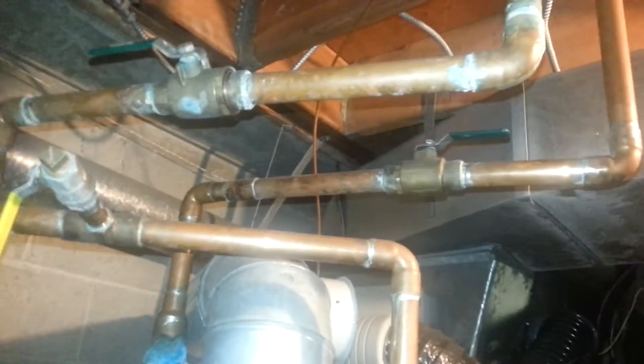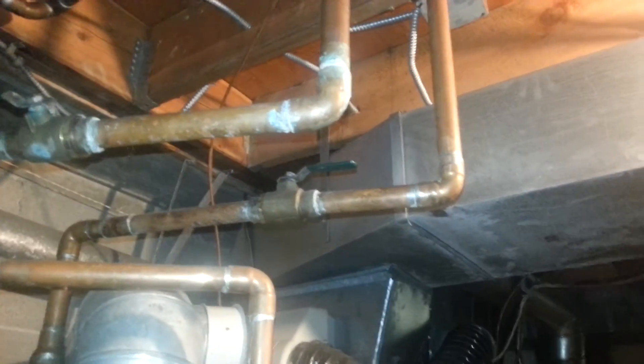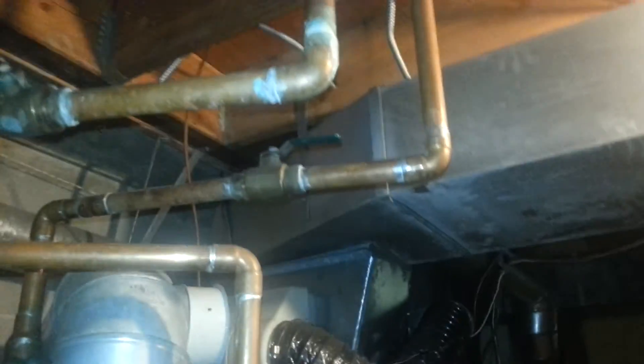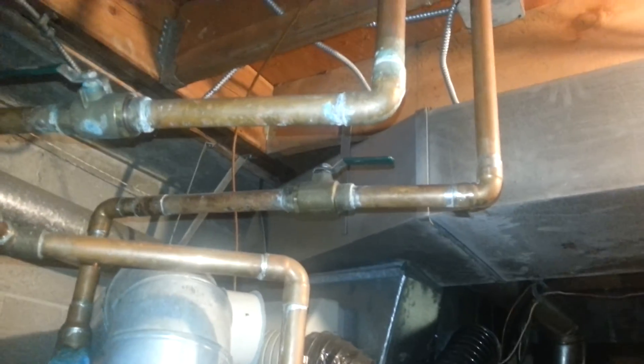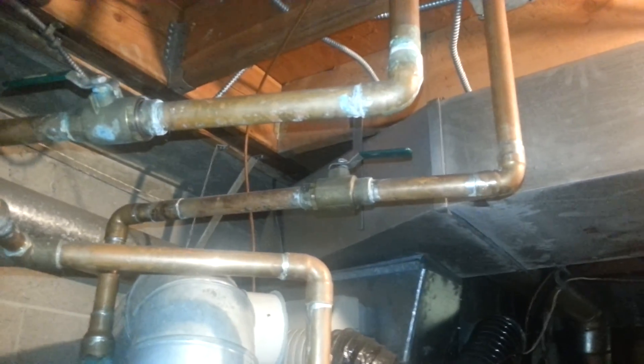So that's what's going on here. Bigger is not always better, and in this case it's definitely worse. You definitely made a mistake by putting one inch for the outlet line for the hot water. Unfortunately, the house has a finished basement, and it's going to be very difficult to replumb this at this point. Thank you for watching.